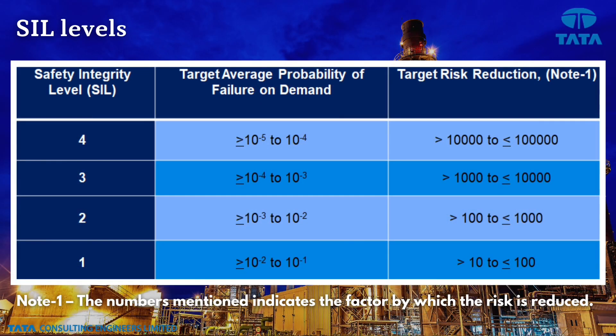As per IEC standards, there are four levels of SIL, from 1 to 4, where 1 is the lowest and 4 is the highest. When SIL 1 is assigned to a loop, the target level of risk reduction is 10 to 100 times; for SIL 2, it is 100 to 1000 times, and so on.